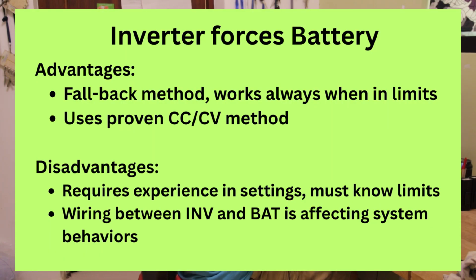So in concept one, the inverter is forcing the battery. The battery is not really resisting anything. The inverter is just giving charge or taking charge, and that's it. The advantage of this concept is that it is the perfect fallback method. It is always working as long as you stay within the limits. The BMS will keep the doors open, so to say, and the inverter or charge controller can do whatever it wants with the battery. The second advantage is it is using the proven method of CCCV. That means constant current and then constant voltage, right? The current will be reduced in that way, voltage will then be kept constant.